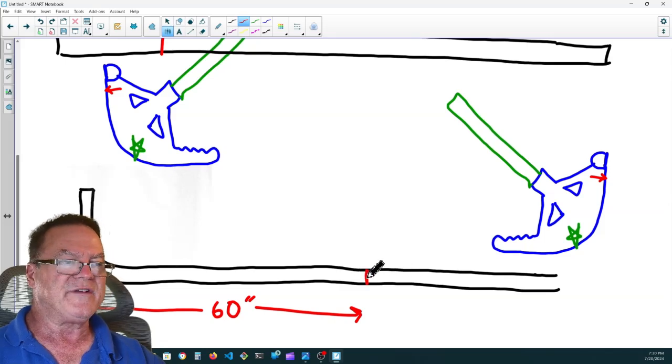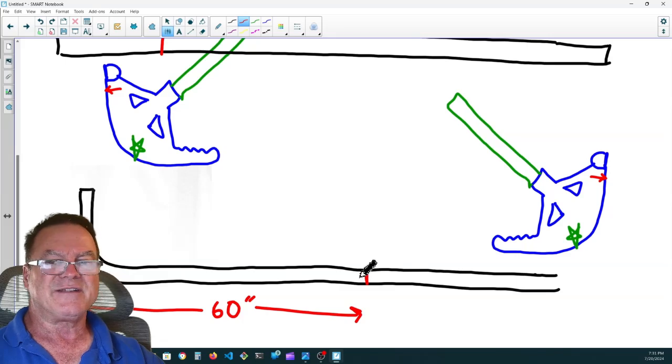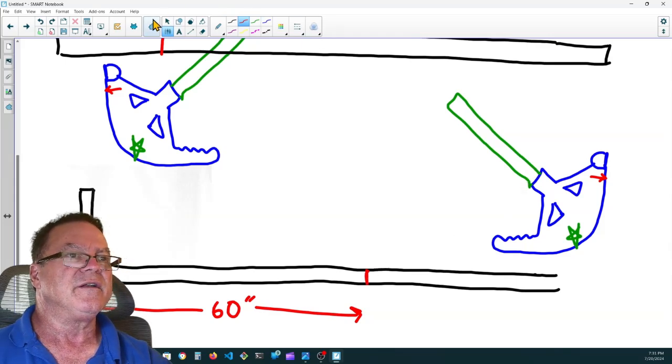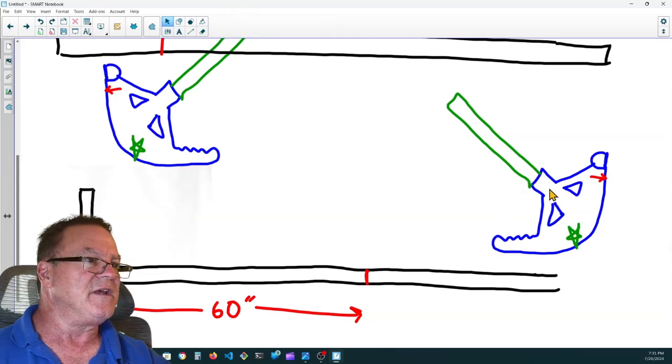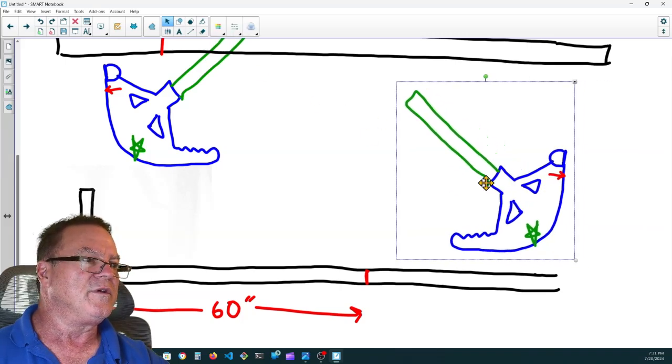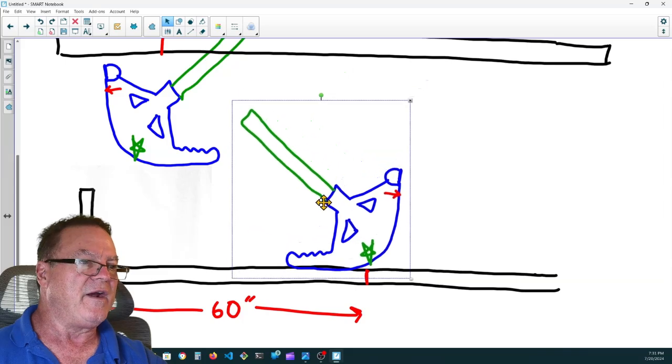We don't have to deduct anything. Don't deduct the take up or anything like that, or the gain, what have you. You put it right at 60 inches. Then we're going to use the star mark on this bender. We'll use the star mark, not the arrow.